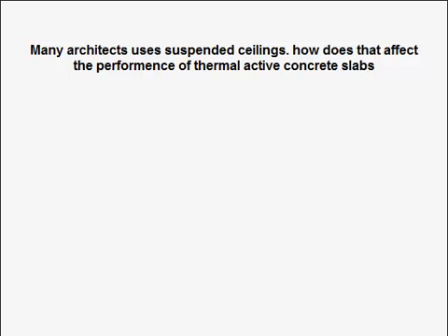There is an option of using open ceilings or perforated ceilings as well, so you've got some exposure of the concrete whilst perhaps not being able to physically see the soffit. That's a sort of compromise solution - it's good, but it will impact on the thermal mass performance to some extent.